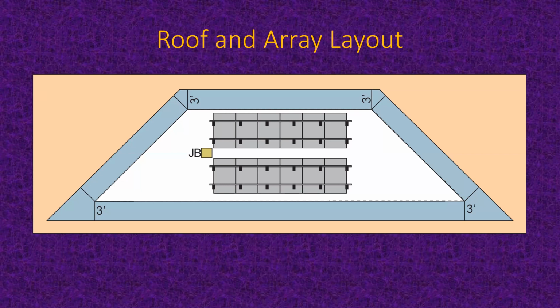and we try to lay them in the middle of the roof to the extent possible, because on the edges the wind pressures are higher, and you have to be a little more fussy about holding the modules down and make sure they'll withstand the upward lift, which in some cases, like down my area here in Florida, it's not unusual to see 65, 70 pounds per square foot of uplift, and you have to design to make sure they don't blow away. Obviously, if your battery backup modules blow away, they're not going to help you much after the storm goes away.